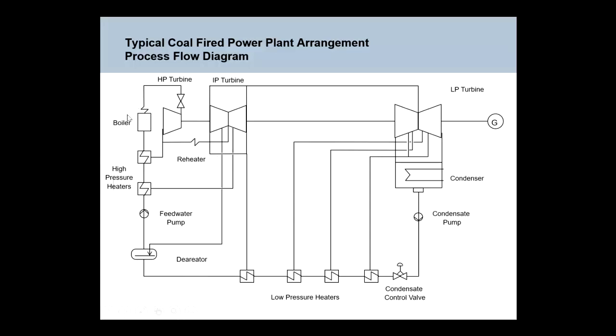This box here diagrammatically is a boiler. The irony is the boiler is actually physically the biggest part of this cycle. So in this boiler, I'm burning coal, and the walls of the boiler are made up of tubes around that sort of diameter, and they are full of either water or steam, depending where in the cycle we're talking about, and they're absorbing heat that's given off by the coal combustion.